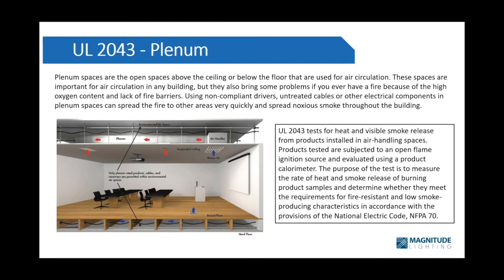You also have airflow down below the floor, and that air is always circulating through. If there was a fire, a non-compliant driver or untreated cables that aren't plenum rated would cause that fire to quickly spread through that airspace and cause more damage. With a compliant, plenum rated driver and lighting fixture, that would deter the fire from quickly expanding throughout the space.